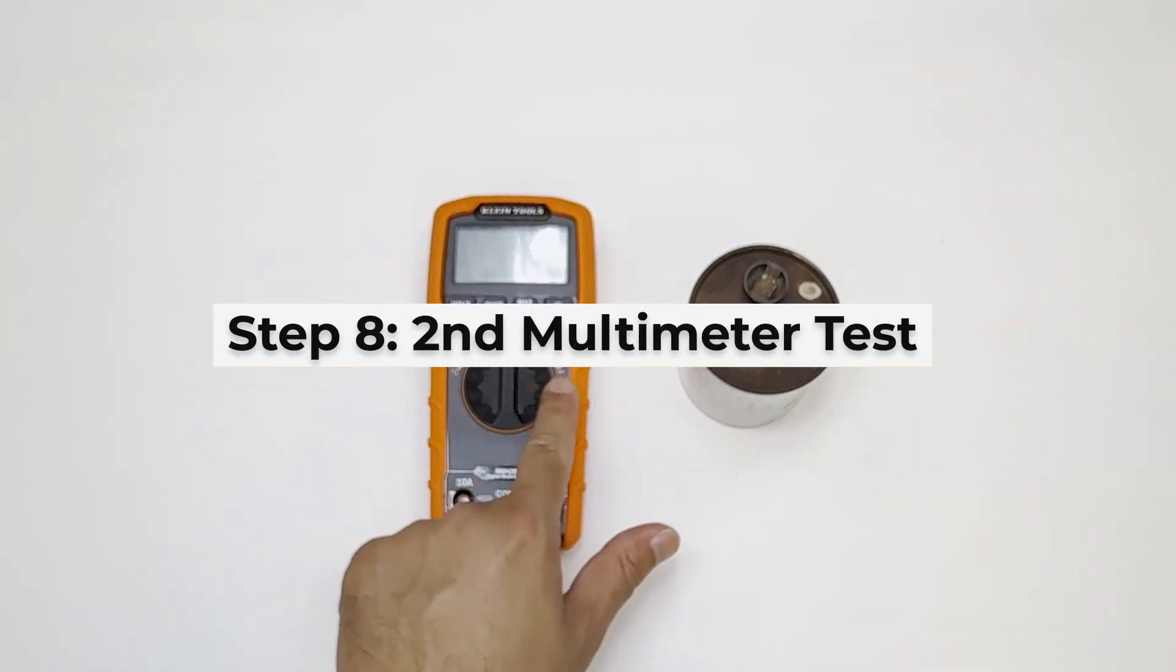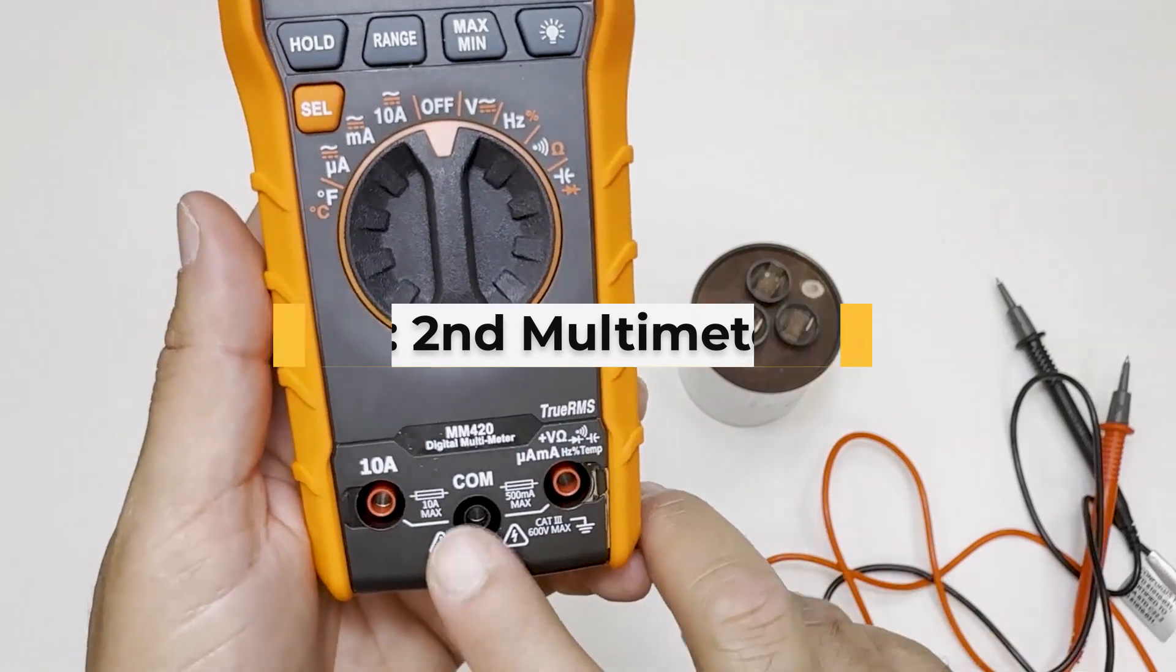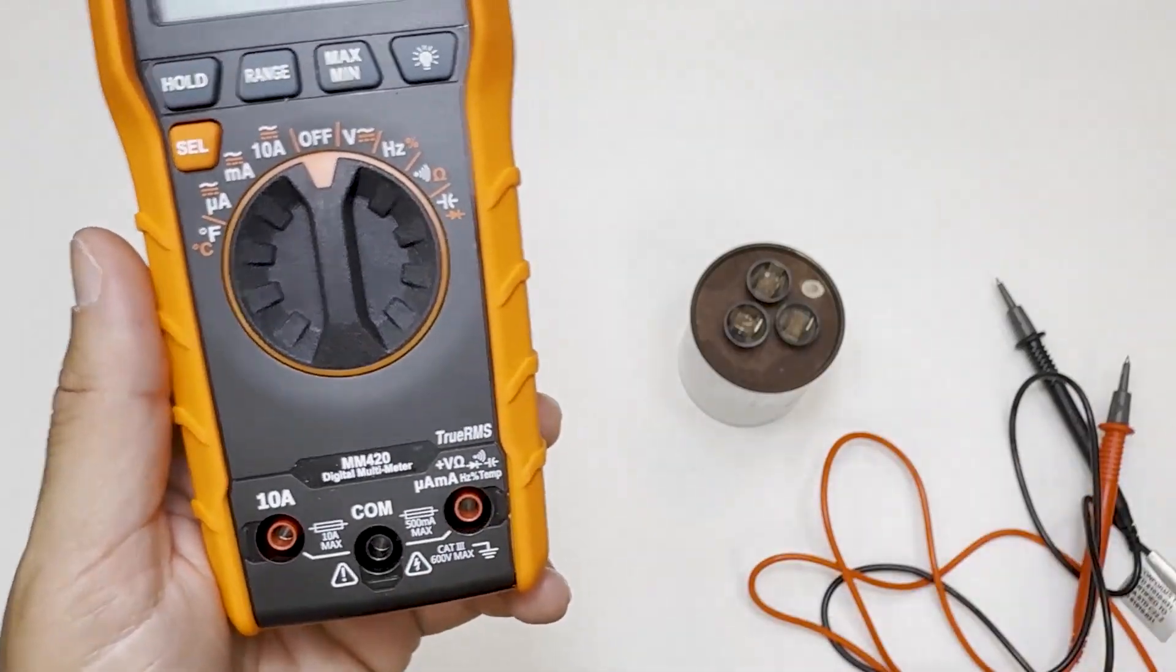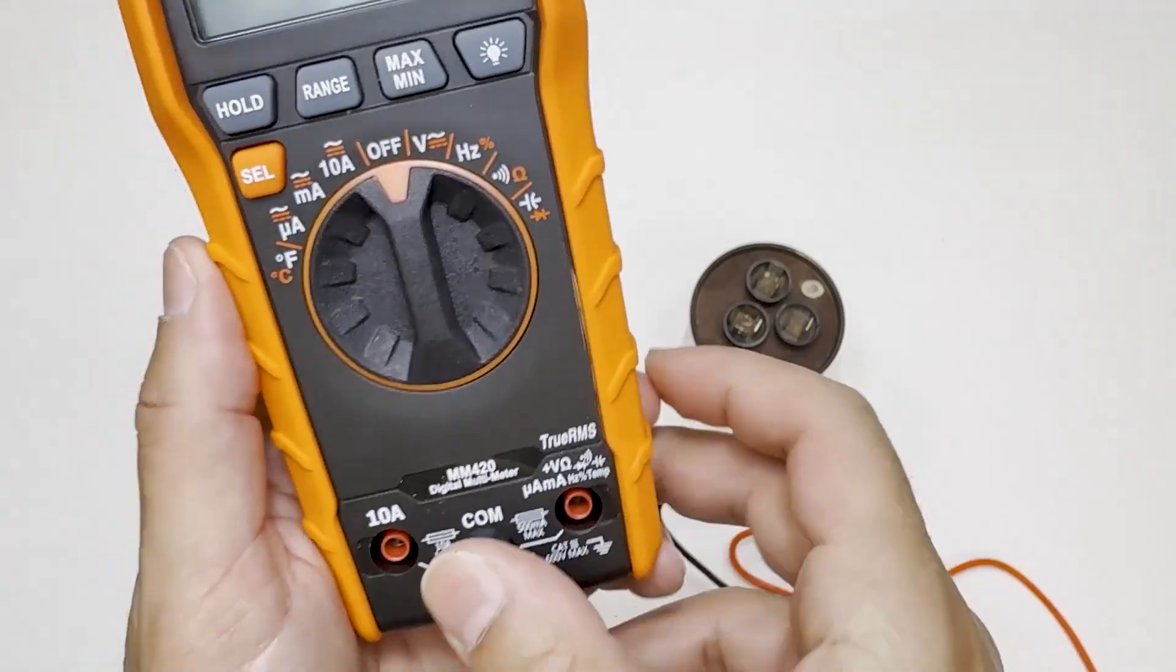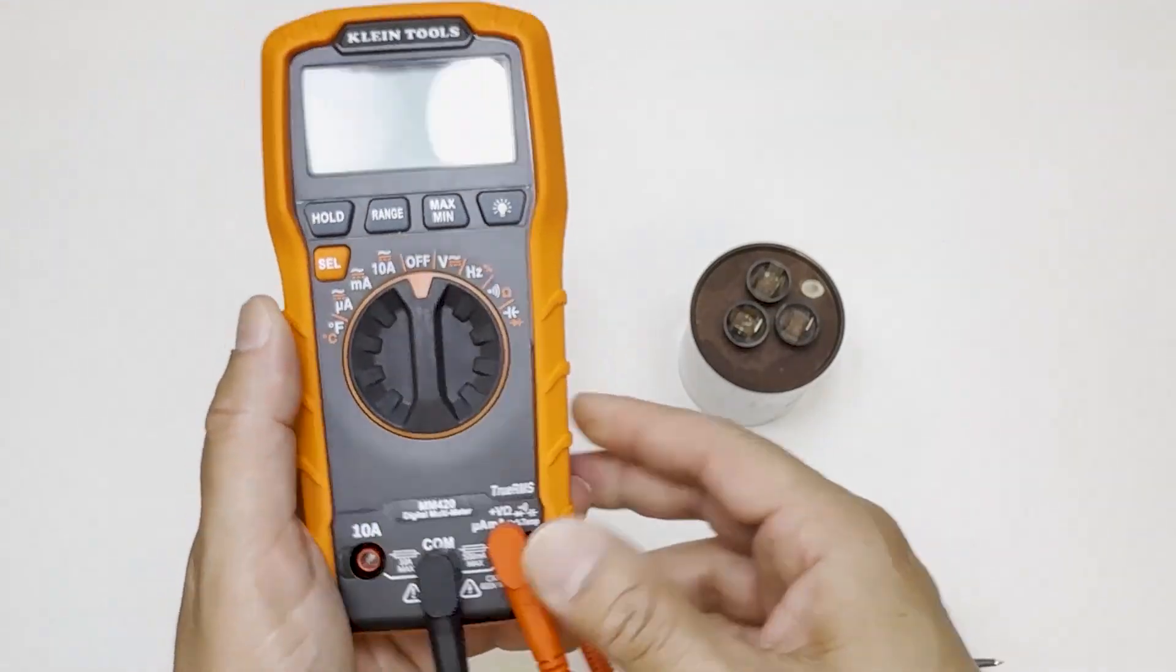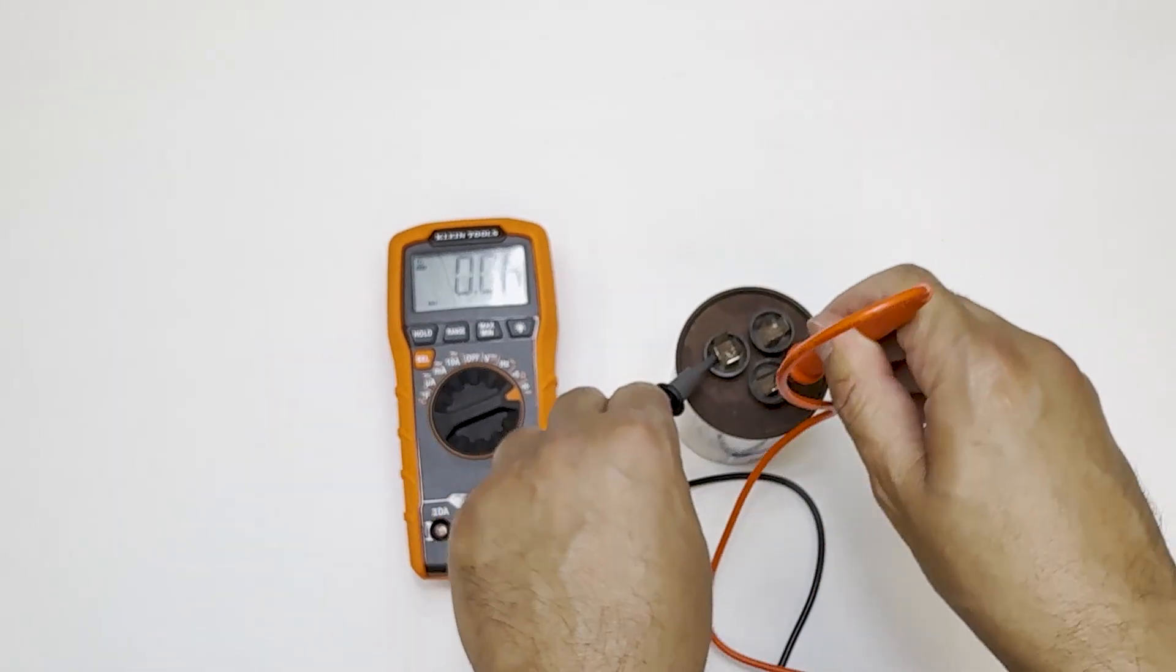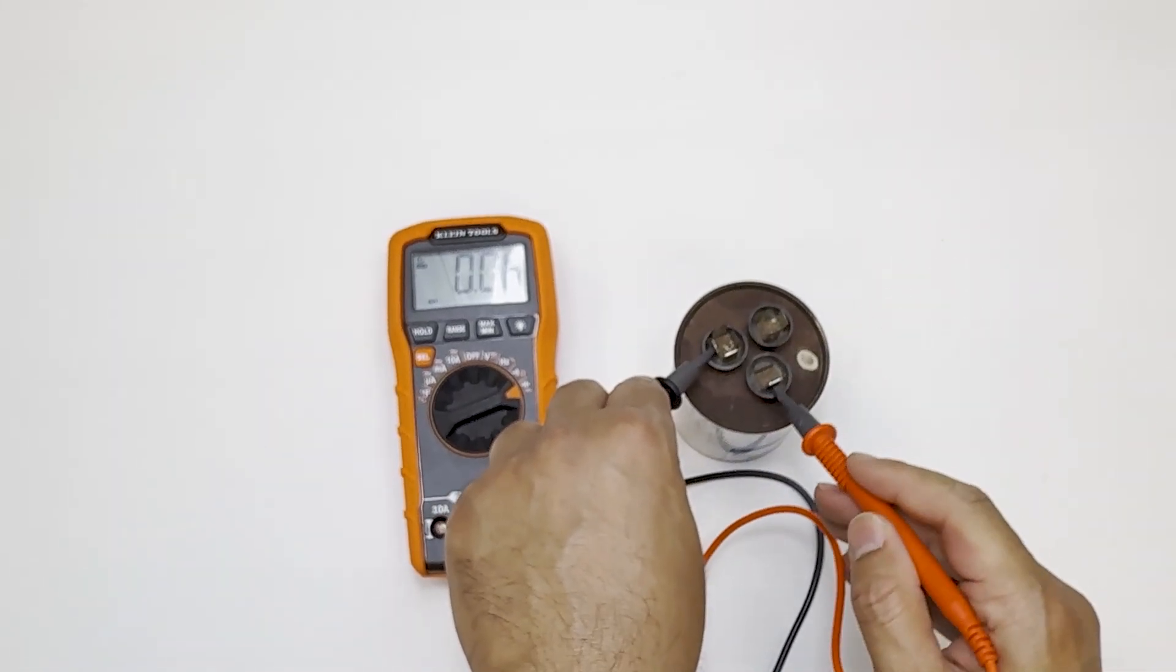Method 2: A multimeter with capacitance mode. Next, we'll use a multimeter that has a capacitance mode to get exact numbers. Step 1 would be to put the black probe in the common and the red in capacitance. Step 2 would be to switch the multimeter to capacitance setting. Step 3 would be putting the black lead onto C and the red probe onto the terminal that you're testing.